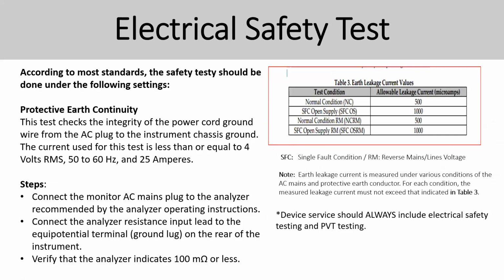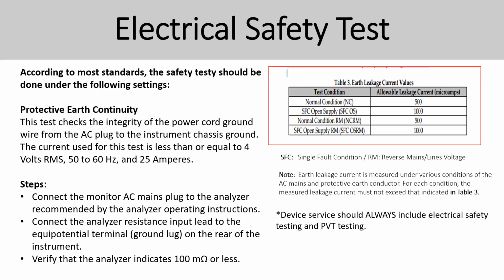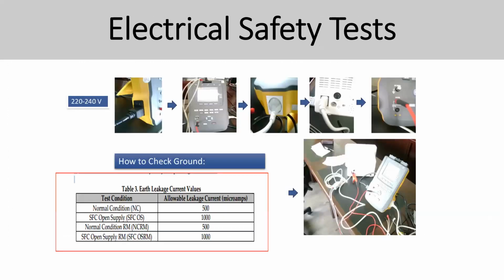So electrical safety is one of the important parts of it. If class 1, you have to do protective earth tests, then earth leakage current, then patient applied part. These are important tests that you're going to do according to the standard 60601 or 62353. So this is the standard checklist that you're going to see for a patient monitor. Then this is the method of doing it by using the electrical safety analyzer.